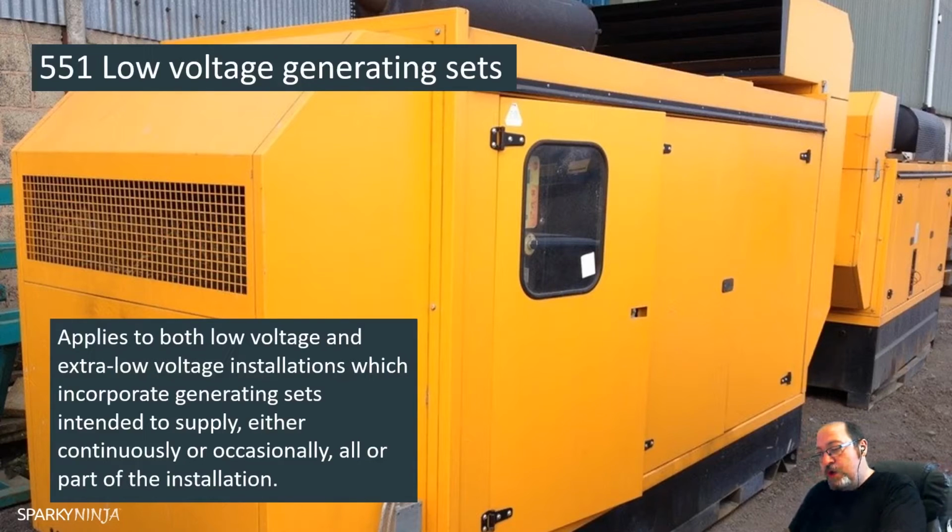So we need an electrical, mechanical, or electromechanical interlock between the operating mechanism or control circuit of the changeover switching device, a system of locks with a single transferable key, a 3-position break-before-make changeover switch, an automatic changeover switching device with a suitable interlock, or other means providing equivalent security of operation. It depends on what you're trying to switch. If it's obviously a static supply of immediate effect, we're going to look at this in the next video in Chapter 56, where we talk about classifications, and we have no break, medium break, long break, kind of things like that. Depending on what the break method or the time allowed is, will depend also on the switchover as well.